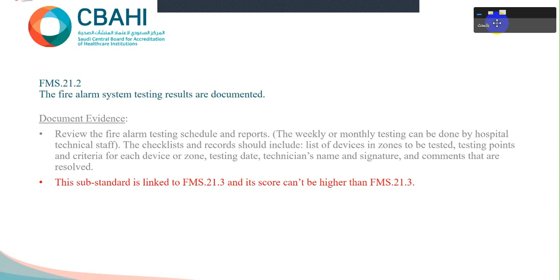The fire alarm system has preventive maintenance. This is very major, and we are looking here for the PPM, which is either monthly or quarterly. But we stipulate in coordination with civil defense that maintenance must be performed by a company or third party certified by civil defense. This is very vital. If you have a PPM monthly done by the hospital or contractor, it's okay. But the quarterly should be done by a company certified by civil defense.